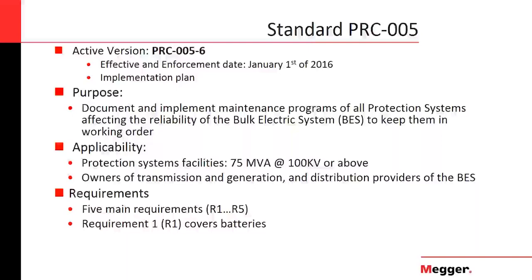The document also defines who needs to comply with this. The owners of transmission and generation definitely need to comply if they are connected to the bulk electric system. And some distribution providers, especially those that have under frequency or under voltage load shedding protection, also need to comply. Now, there are other, more specific criteria. These are like the general criteria. There's one specific criterion that protection system facilities that work on systems of 75 MVA at 100 kilovolts or above. So there are some specific details. Obviously, this is covering just the basics, and we encourage you to review those documents to be more informed about this.